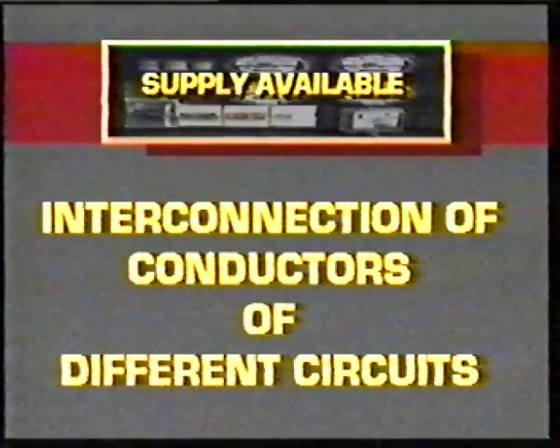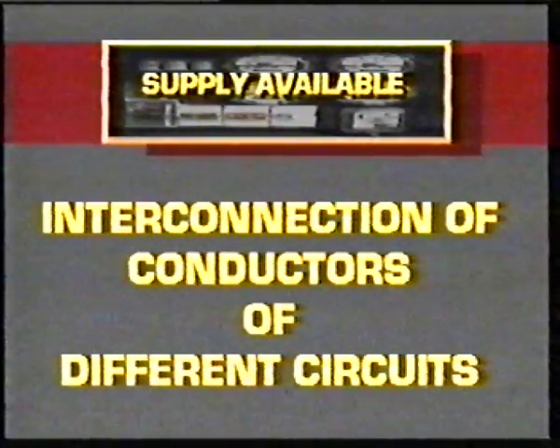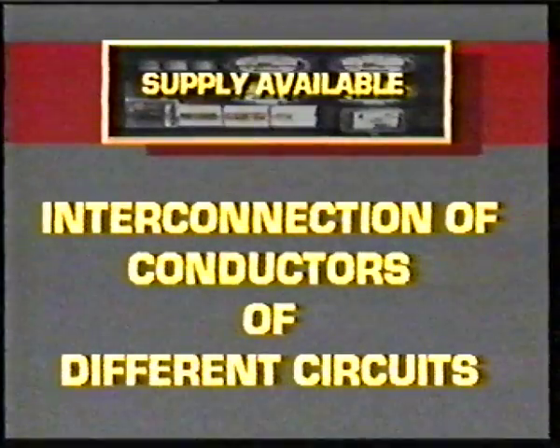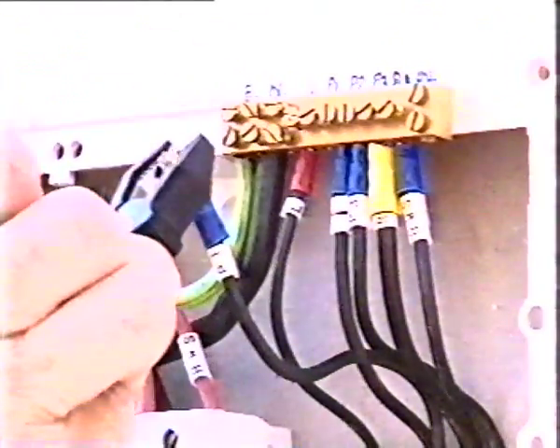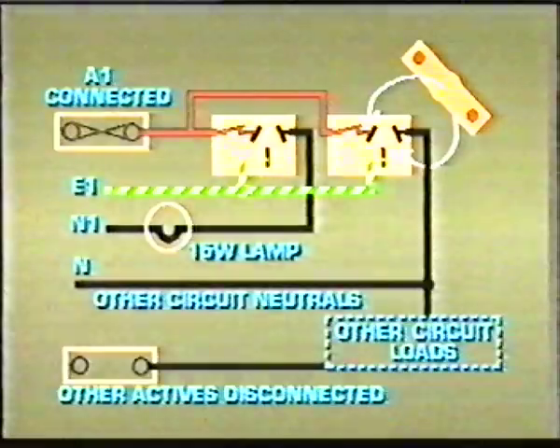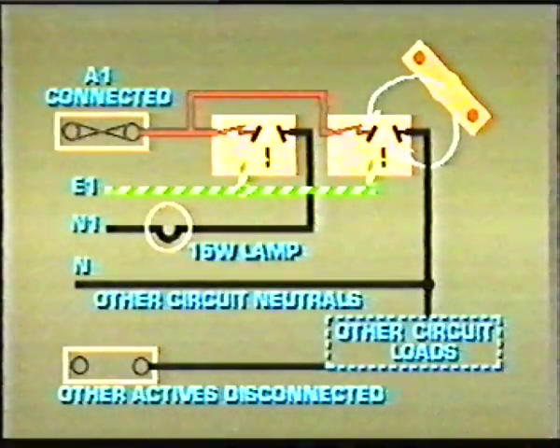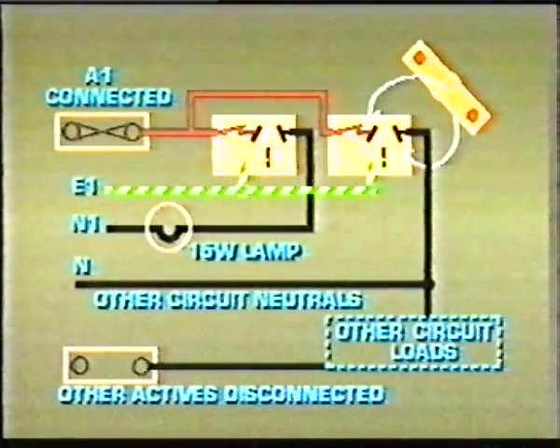Interconnection of conductors of different circuits can be tested using test lamps and a 15-watt lamp. As in the test for transposition of the neutral conductor and earthing conductor, the neutral conductor of the circuit being tested is disconnected from the neutral link. A 15-watt lamp is then connected between the neutral conductor and the neutral link. A correct connection will be indicated by a dull glow when the test lamps are connected between active and neutral.